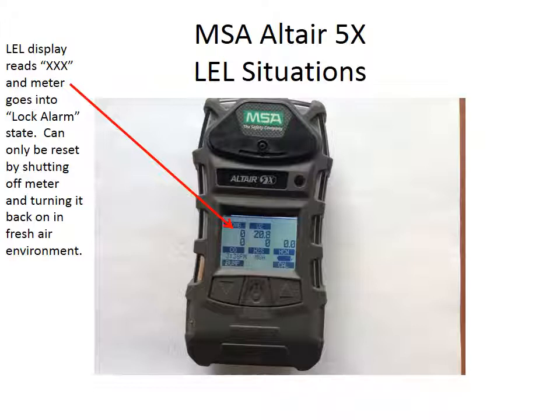Okay, so what does the meter actually do when you hit LEL? Good, important thing to understand. What's going to happen is the LEL display, or that combustible gas flag, COMB, up on the top left of the screen, is going to convert from an actual value, if you were at 50% LEL or 70% LEL, it's going to go into an alarm, and that value is going to convert to XXX. MSA calls this a lock alarm state. This is their proprietary name for it. And this meter can only be reset by shutting the meter off and turning it back on in a fresh air environment once it's in the lock alarm state. So it's important to know that's what's going to happen, and the only way to reset it is to move out to that fresh air environment.